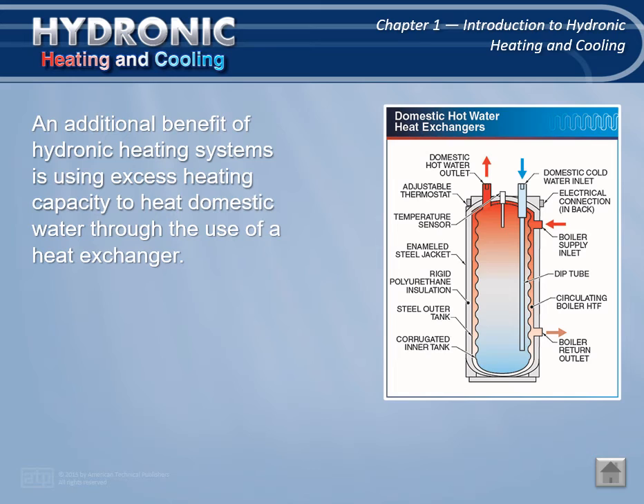Hydronic systems cost less to operate and maintain because of the durability and long life of the equipment. In both winter and summer, domestic water can be heated using the same boiler that supplies hydronic systems. The three ways this can be done are a combination boiler, an additional heat exchanger, or an indirect fired water heater installed in the boiler.